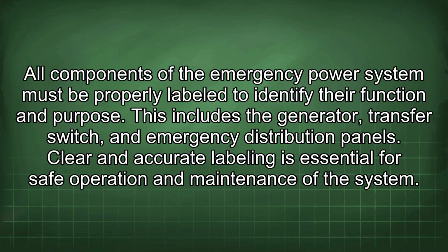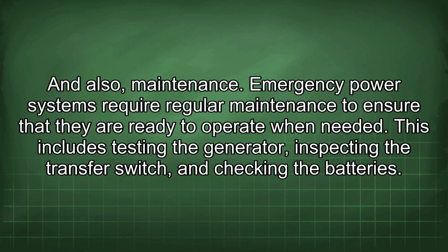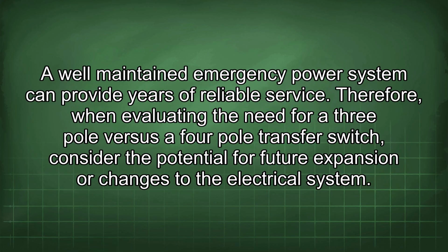All components of the emergency power system must be properly labeled to identify their function and purpose. This includes the generator, transfer switch, and emergency distribution panels. Clear and accurate labeling is essential for safe operation and maintenance of the system. And also, maintenance. Emergency power systems require regular maintenance to ensure that they are ready to operate when needed. This includes testing the generator, inspecting the transfer switch, and checking the batteries. A well-maintained emergency power system can provide years of reliable service.